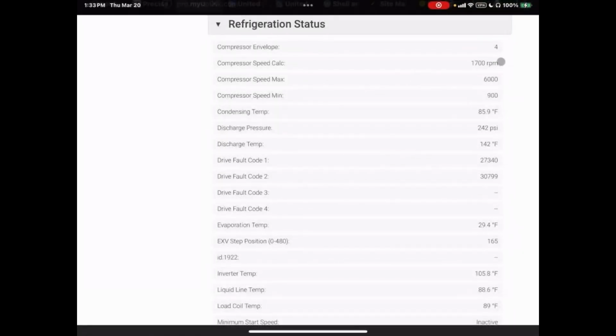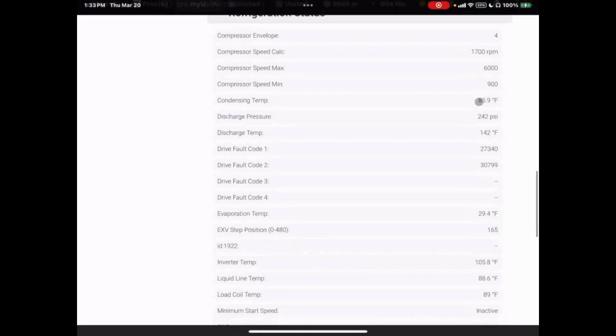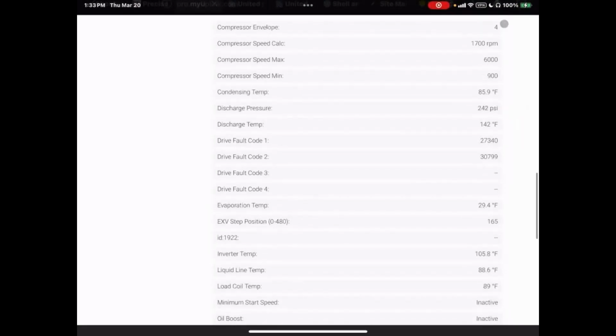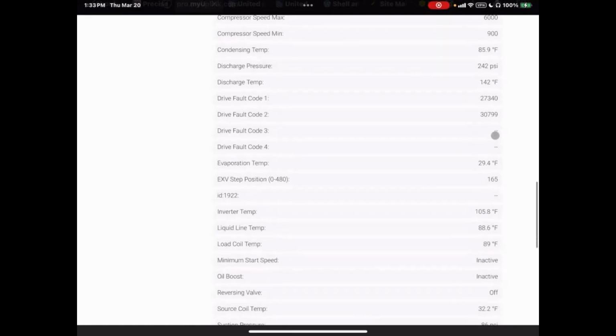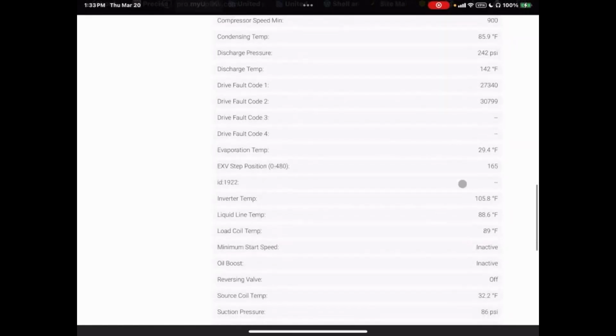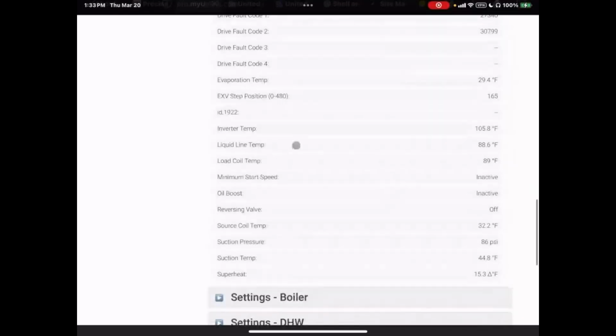You can see here that we're running in compressor envelope number 4, and we can see what the calculated RPM is and what the max and minimum speeds are. These will change based on which envelope condition we're in. It's going to give us things like discharge pressure and suction pressure and EXV step positions and all sorts of information here. We can actually see what the temp is on the inverter. A tremendous amount of information is available here, but all of these are just a snapshot in time.